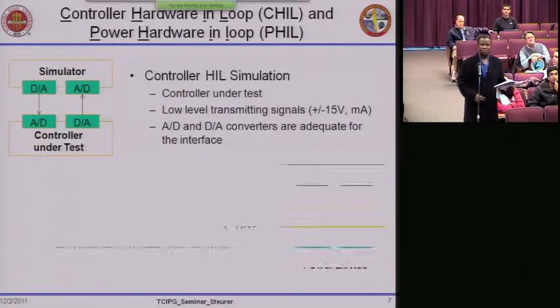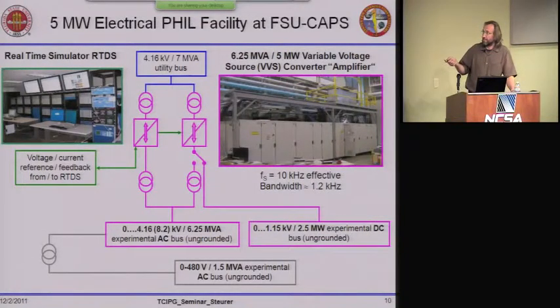Well, okay, I can show you. To me, the interface consists of the actual power amplifier, and then the algorithm for how you implement the feedback from the real world back into the simulation. Those are two pieces. The actual physical interface in this case is a back-to-back converter system. Behind this, in this cabinet, there's a bunch of IGBTs—insulated gate bipolar transistors—that switch at 2 kilohertz and rectify power from the grid into DC. Then in this cabinet here, there's an inverter stage that, by reference from the RTDS, modulates the output such that it recreates that waveform. And all this, of course, in a high-power device like that, involves control systems, protection, and all sorts of things.